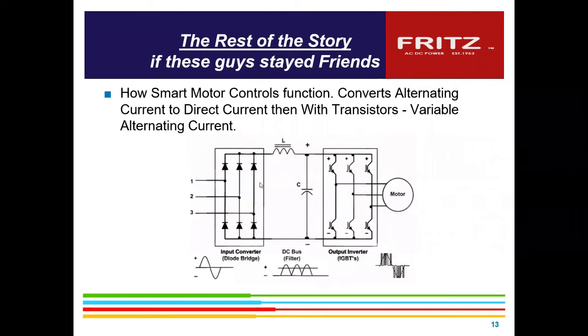So when they came out with the variable frequency drive, what it is basically doing is taking the sine wave power that we get from the power company and converting it to DC power. Then with the DC power, they have these filtering capacitors and what they call a link choke inside, to basically slow down the electronics so you don't get a lot of surging in power. Sometimes they'll also put line reactors out front, just to help with surges and pulses.